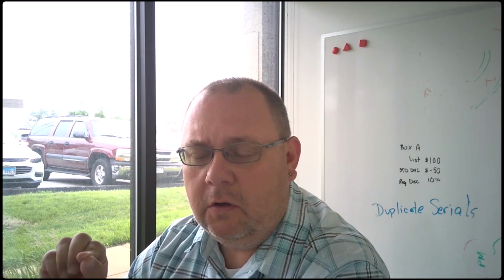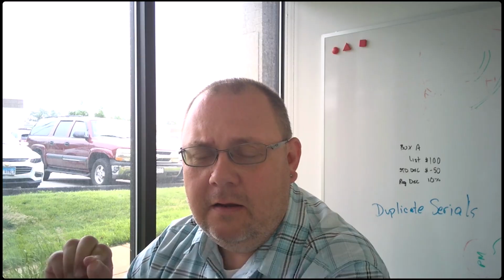And I will tell you that when I did this a few months ago, it has to be a very specific PDU. I think they only support APC PDUs, or the ones that verify the OIDs for the PDUs. So it can be done, but they're very rigid in which ones you can use. You can't just go out and get a Vertiv or whatnot. They have to support specific APC PDUs.